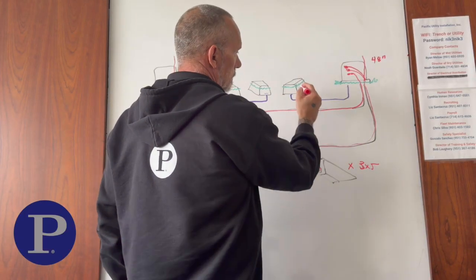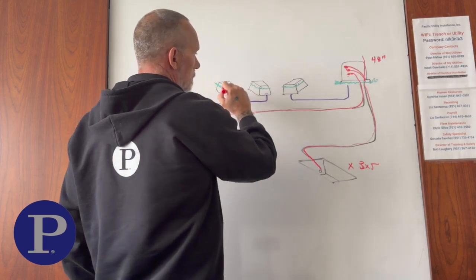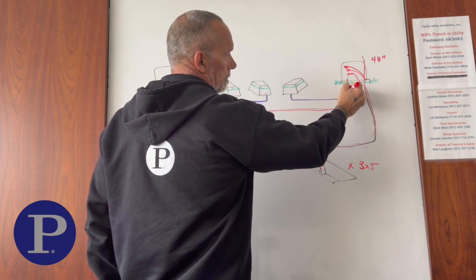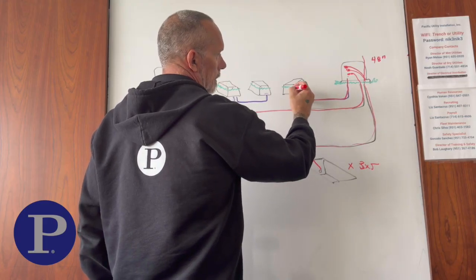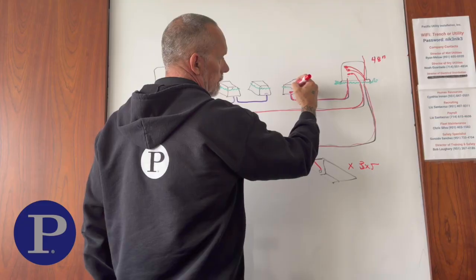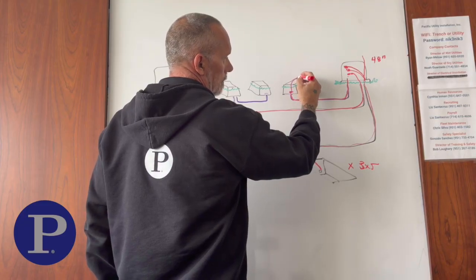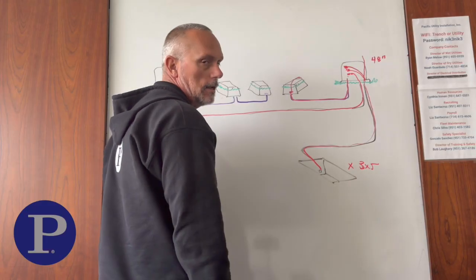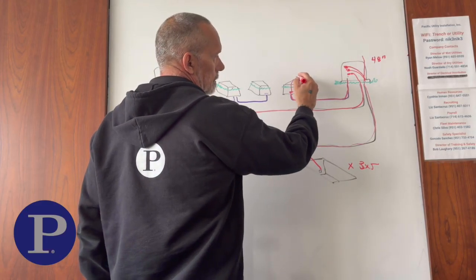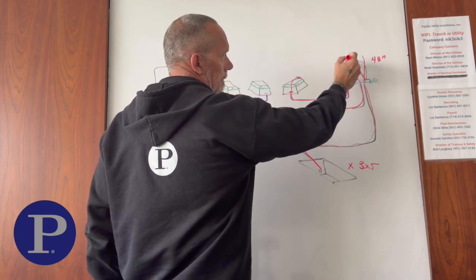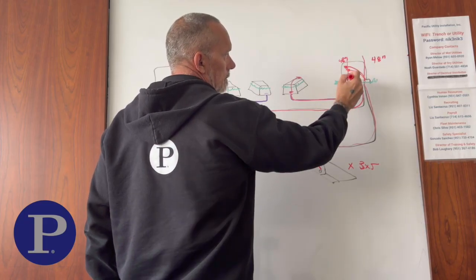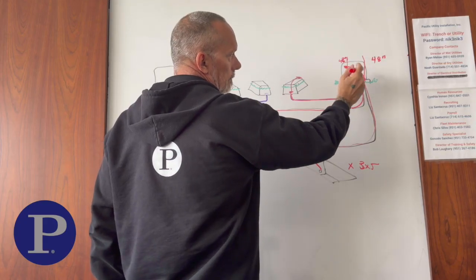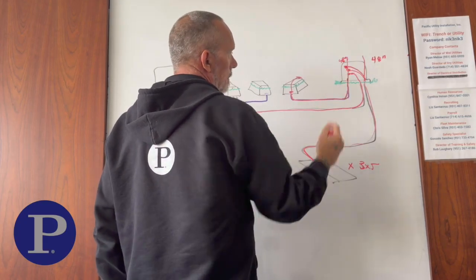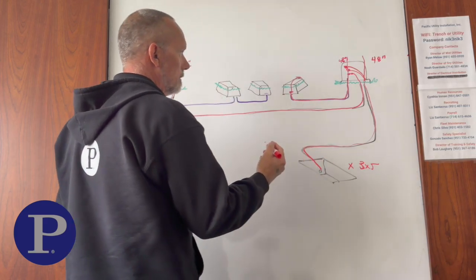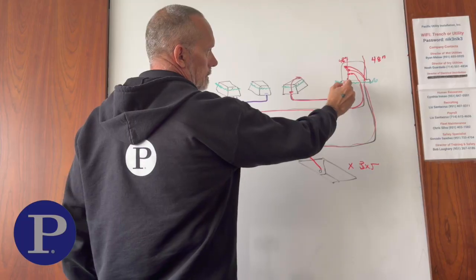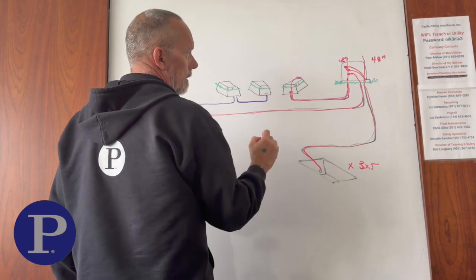Your secondary side, which is going to be your transformer, is going to feed all these handholes in between. You're going to pull it in here. It's going to come up into the handhole, your duct being on one side. You're going to pull the cable up and cut it just outside of the rim of the handhole. Once this cable is cut here, make sure that this comes up about 48 inches up here. That'll give you enough room when the transformer gets set to lay the cable over, make your splices, and connect it all up. This right here kind of shows this transformer is going to feed one handhole here.